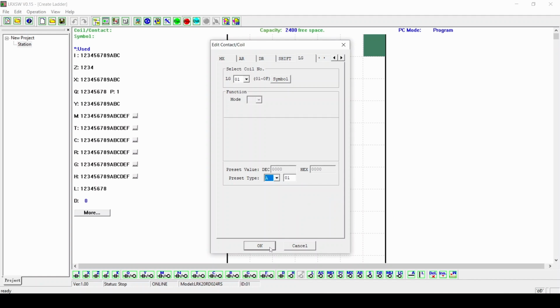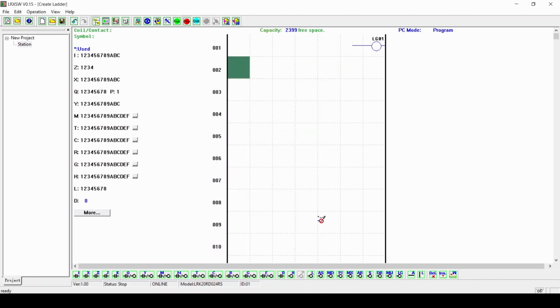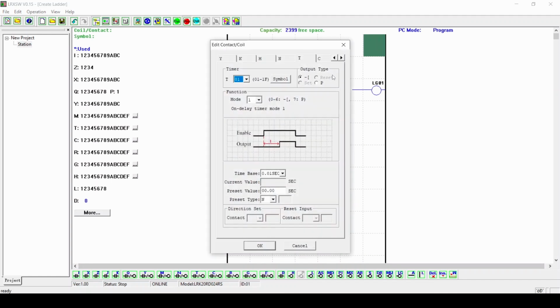Now, set the data log sampling time. Add a timer on the first line in pulse work mode. In the timer configuration window, set the on and off times, which represents the data log sampling interval. To record a sample every 10 seconds, for example, set an on time of 1 second and an off time of 9 seconds, like this.